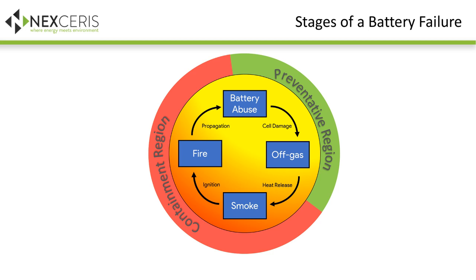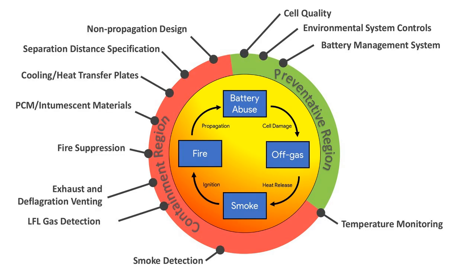What this leaves us with is two regions that we look at. One is a preventative region. The preventative region is where we want to put most of our controls and fault detection, because these are areas where we can still prevent a cell from going into thermal runaway. The containment region is where we see most of our smoke and fire detection as well as fire suppression. Those are points where we're trying to prevent that cell from causing other cells to go into failure.